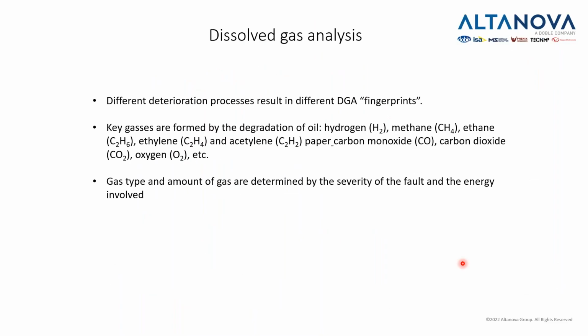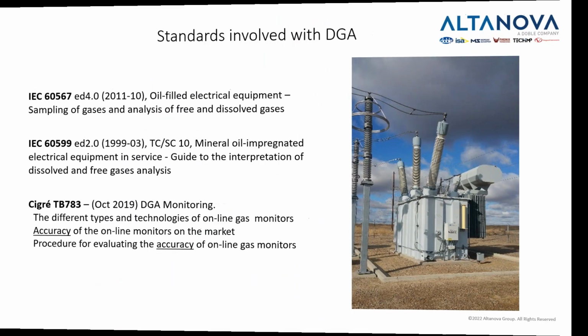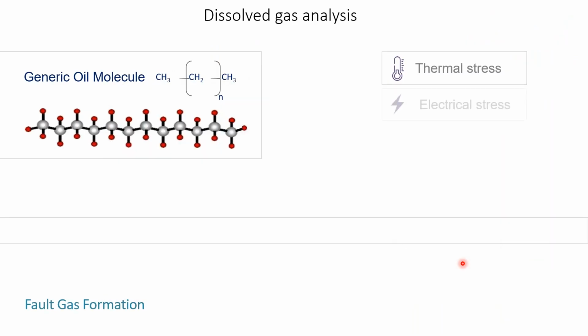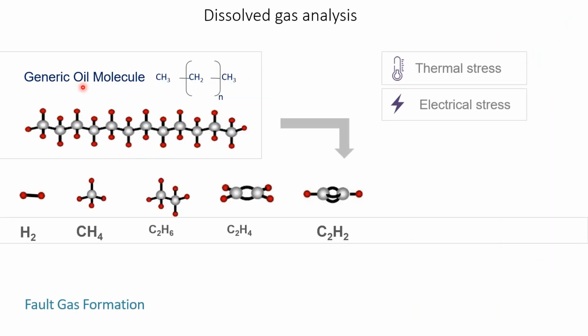And as I mentioned, the reason why this happens, just a second, I want to show you this first, is because the oil is an organic compound. And when the organic compound is stressed, whether through high temperature, or through sparks, which is a PD, or through arcing, then this chain will break. And first you will have the hydrogen dropping off, and then you will have the methane and ethane and acetylene and ethylene, etc., etc.